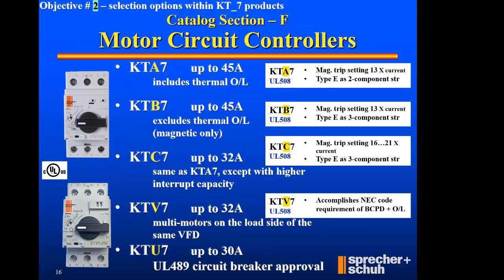So what are the differences between those? I'll have to say that KTA is probably the most popular controller, and that is what is consistent of a two component type E starter. Typical magnetic trip setting of 13 times the inrush current. So KTA includes a thermal overload relay. 2-component starter. Moving downward to a KTB, well, what's the difference?